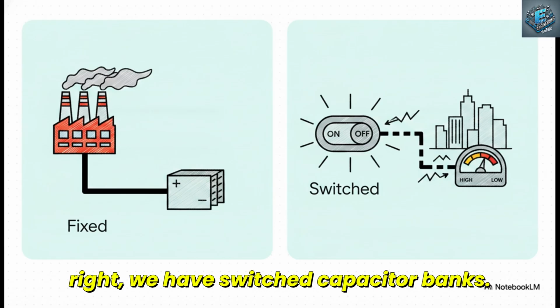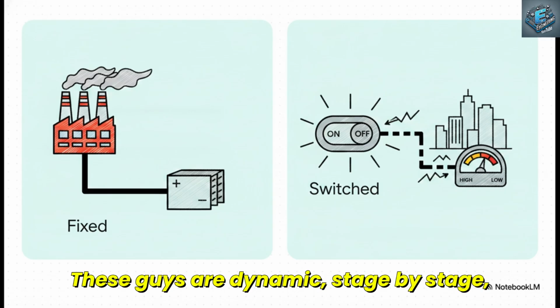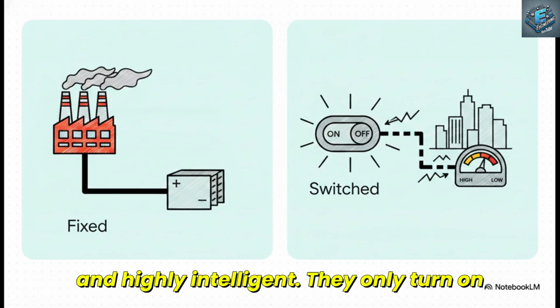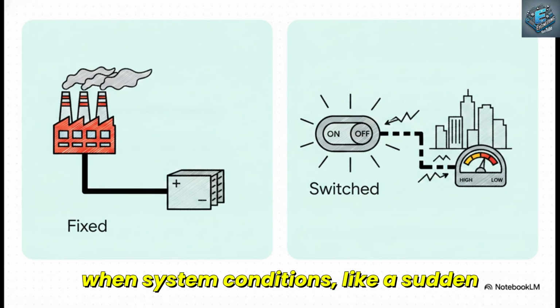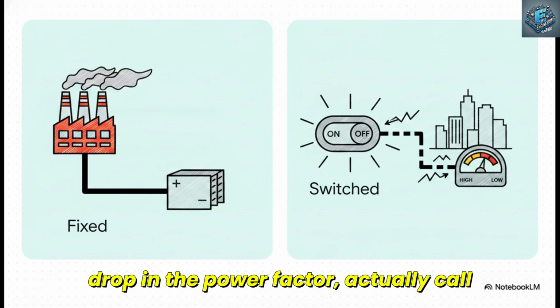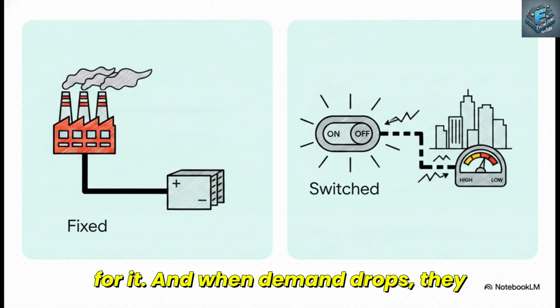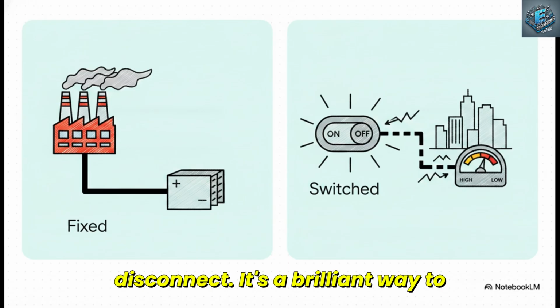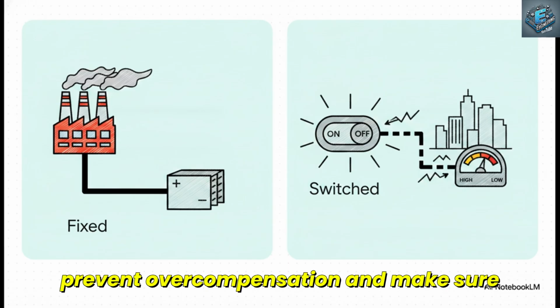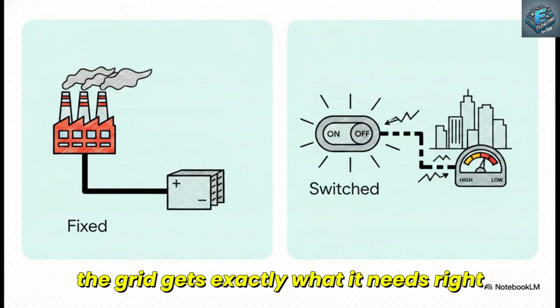But on the right, we have switched capacitor banks. These guys are dynamic, stage by stage, and highly intelligent. They only turn on when system conditions, like a sudden drop in the power factor, actually call for it. And when demand drops, they disconnect. It's a brilliant way to prevent overcompensation and make sure the grid gets exactly what it needs right when it needs it.